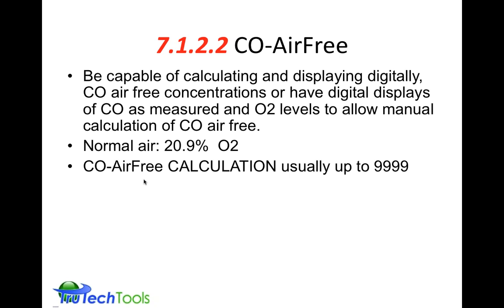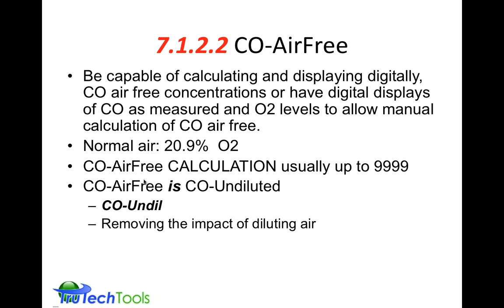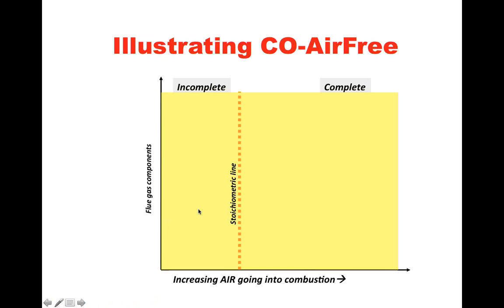So normal air is 20.9% oxygen, and the CO air-free calculation usually tops out at almost 10,000. CO air-free sometimes is also called CO undiluted or CO undilute or undil. It's basically removing the impact of the diluting air from the calculation of CO. And this is from my webinar on combustion analysis. And we're going to talk just a little bit here about how to illustrate the concept of why CO air-free is of interest.